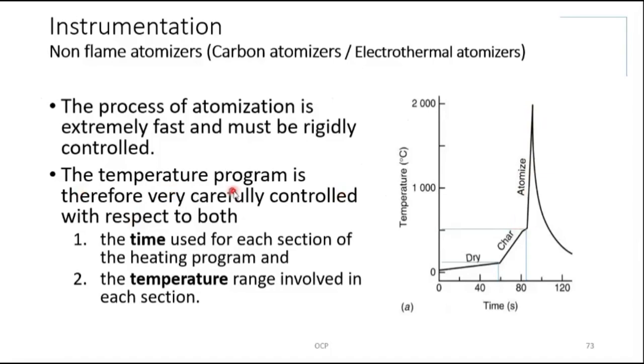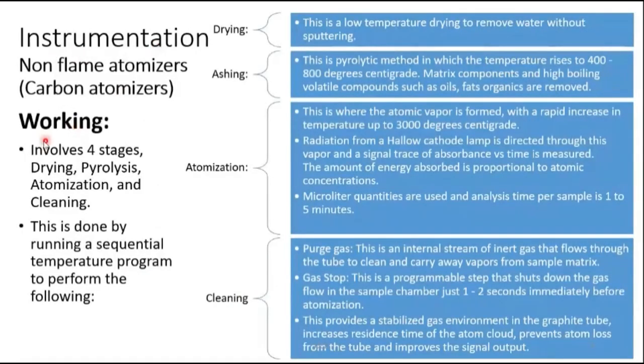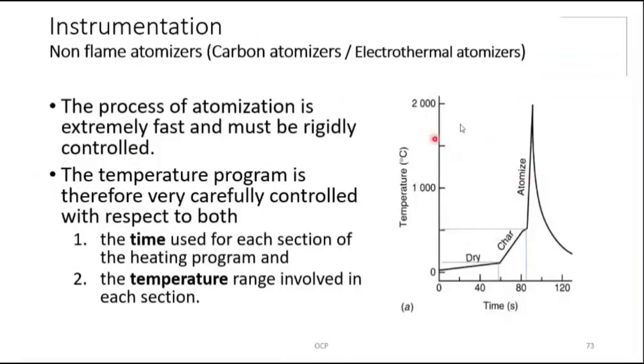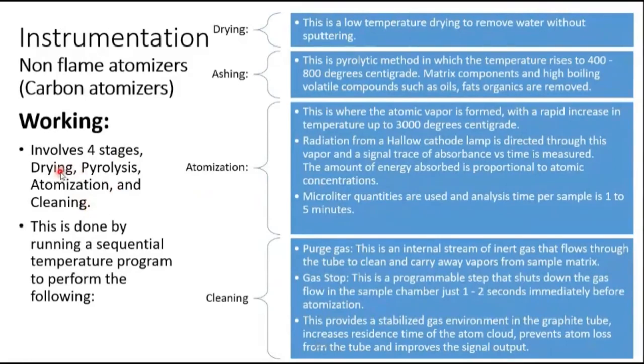The temperature program is therefore very carefully controlled with respect to both the time used for each section of the heating program and the temperature range involved in each section. The instrumentation involves four stages: drying, then pyrolysis (converting to ash), then atomization, and after atomization, cleaning whatever residue remains in the cylinder.